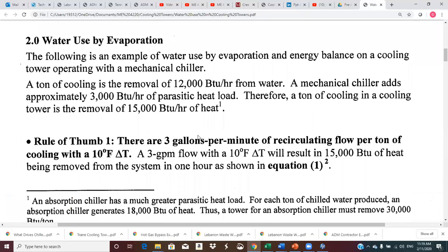Okay. So we're going to move on to point 2 here, water use by evaporation. So we remember that a ton of cooling, a ton, is a rate of energy transfer. So it's 12,000 BTUs per hour. And usually in a chiller, we're removing it from water. A mechanical chiller adds roughly 3,000 BTUs per hour of parasitic load. And so what this is looking at is that's roughly a kW per ton into the compressor.